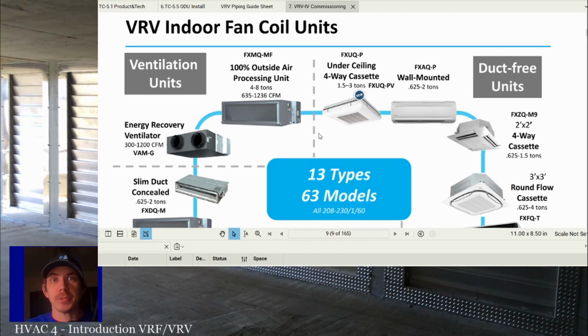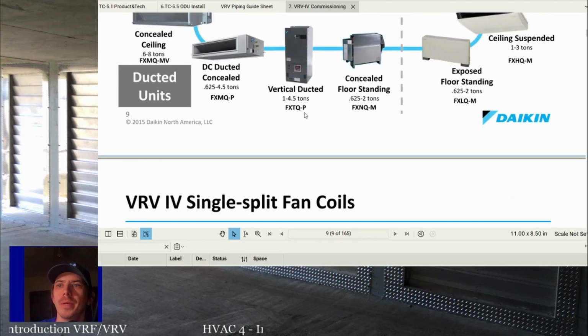Because what VRF and mini splits are good at is adjusting the amount of capacity being used at any amount of time, ramping from anywhere from 20% of capacity to 120% of capacity. There's a large range that it can accommodate as far as load to save energy. And when you're talking about outside air, you're generally going to be dealing with something that's always got to be running at a very high stage, I guess. For the most part, I think it's starting to come around, but for a long time other manufacturers didn't recommend using these units because it's just too much on the total system. Even though 8 tons is nothing to a VRF system, it's still a lot of tonnage to not be able to modulate with.